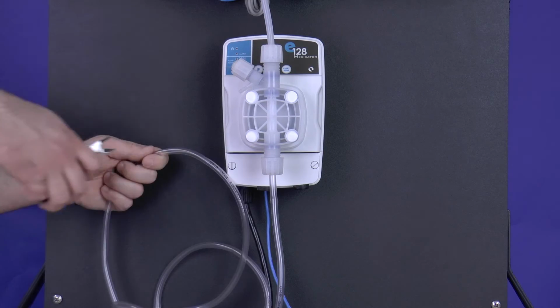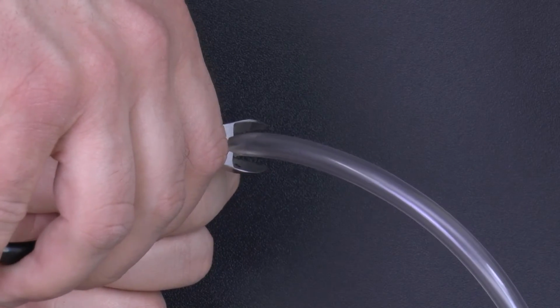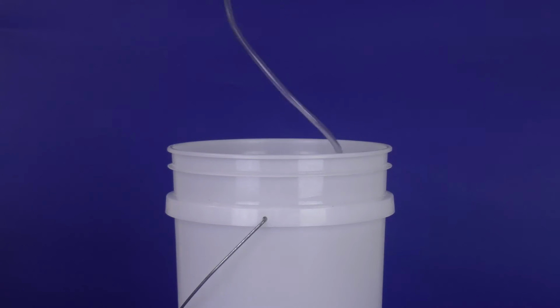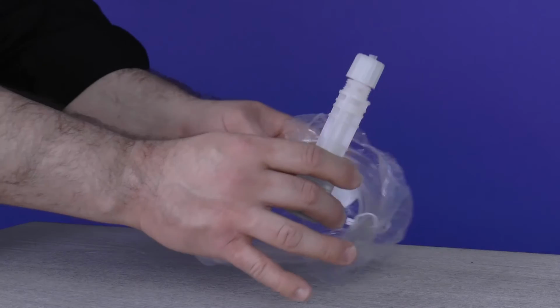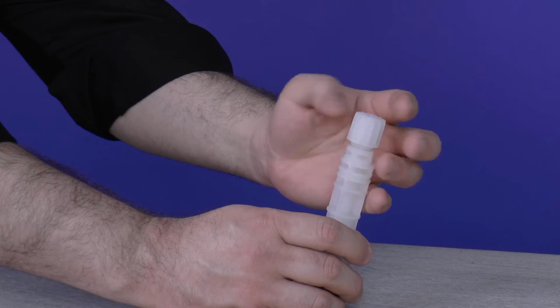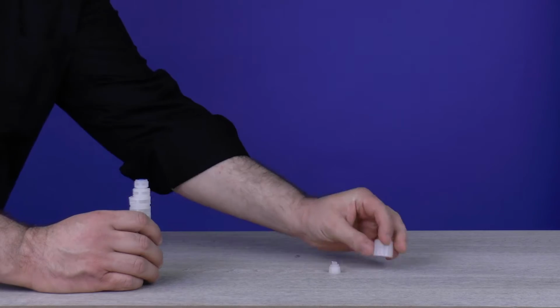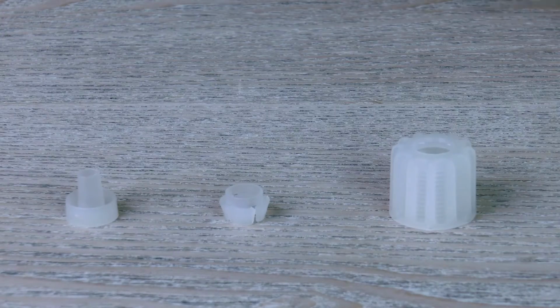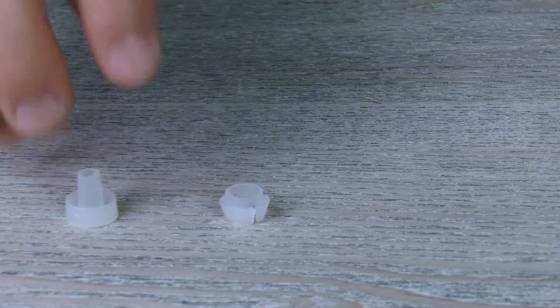Foot filter. Next, cut the PVC suction tubing connected to the suction valve so that the foot filter comfortably sits in the chemical bucket in a vertical position. Grab the foot filter from the installation kit and remove its tube nut, collar, and nozzle. Only hold on to the foot filter tube nut since you will need it for the next step. Set everything else aside, but make sure not to lose these items.